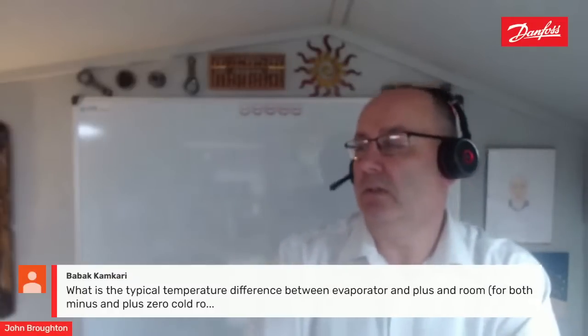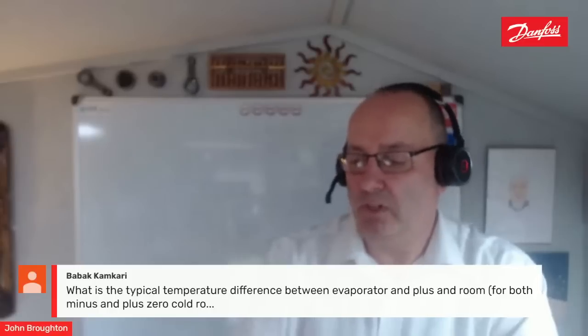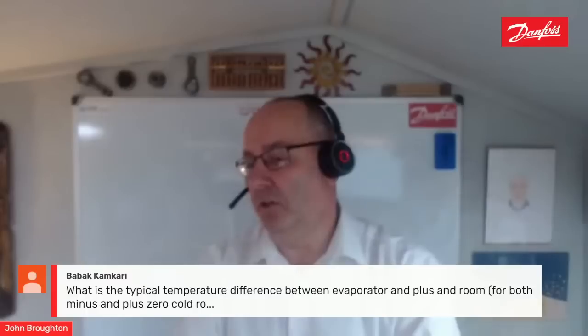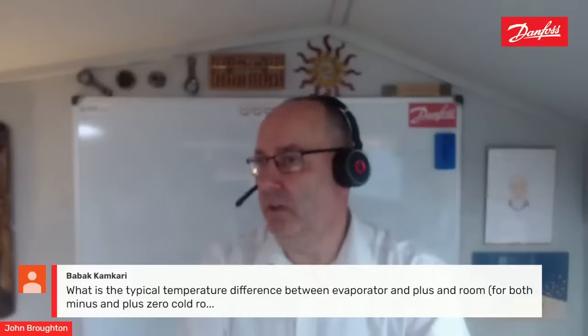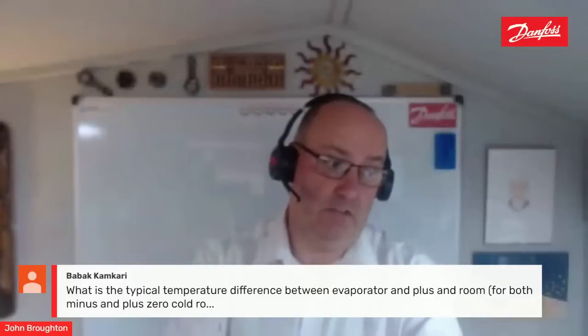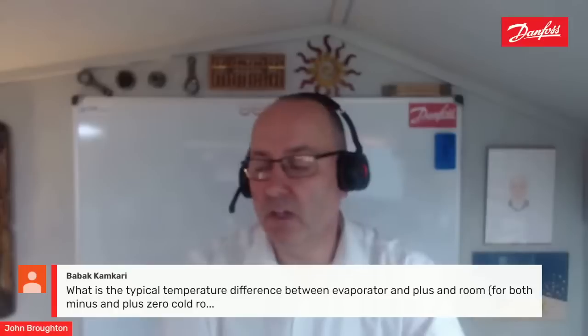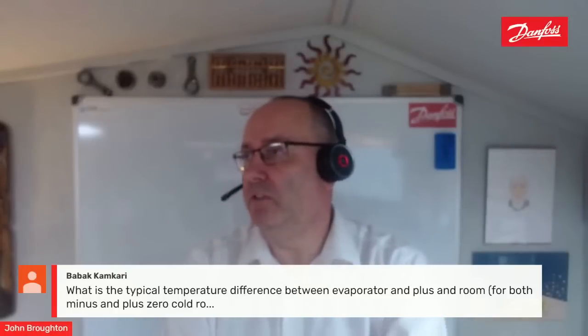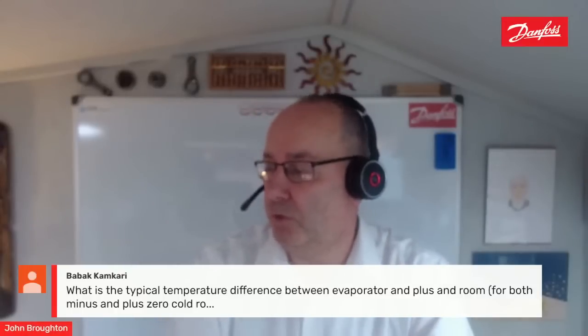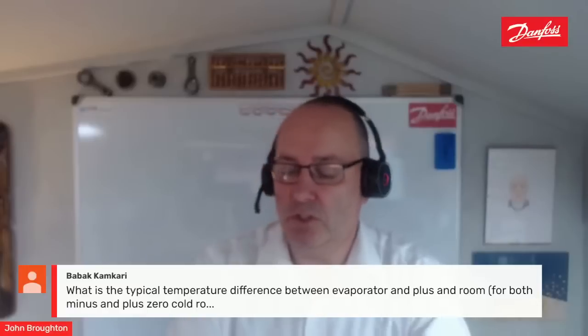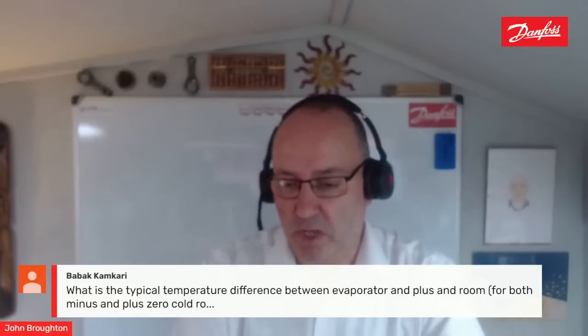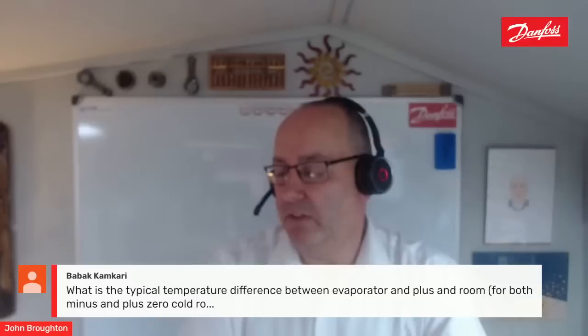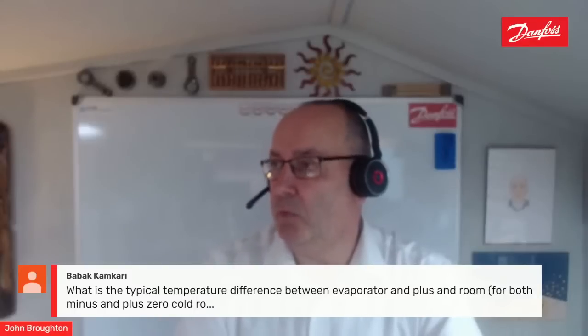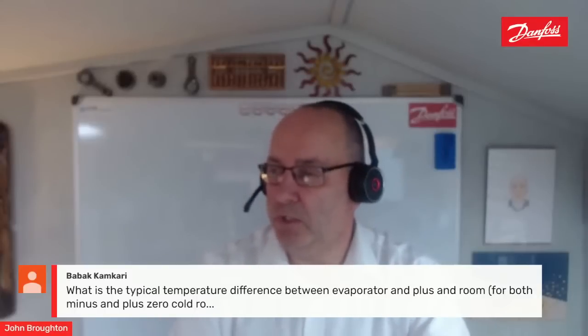Then if we're talking above freezing, a positive temperature room, it really depends on the product that you're storing in there. Every product needs a different humidity. For fruit and vegetables, meat, fish, there's lots of information on the internet, and I've got lots of information here in front of me on what you need for a specific product. If you have, and we'll take meat for example, a very high humidity, then the meat can get a little bit slimy.